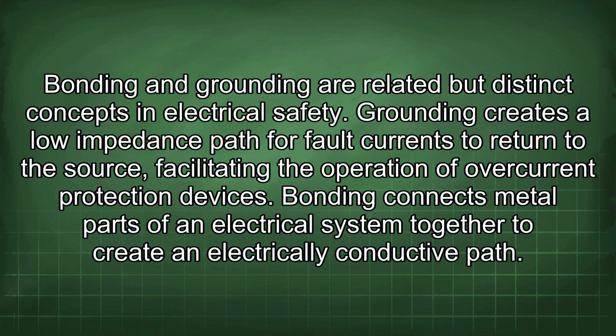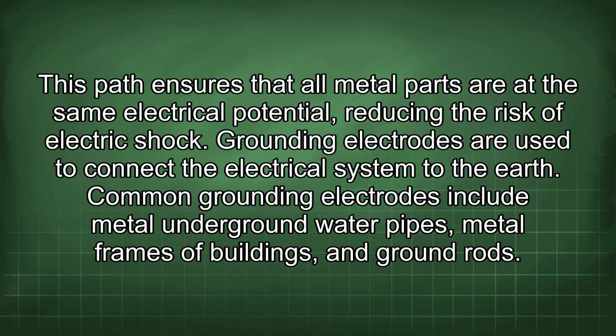Bonding and grounding are related but distinct concepts in electrical safety. Grounding creates a low impedance path for fault currents to return to the source, facilitating the operation of overcurrent protection devices. Bonding connects metal parts of an electrical system together to create an electrically conductive path. This path ensures that all metal parts are at the same electrical potential, reducing the risk of electric shock.